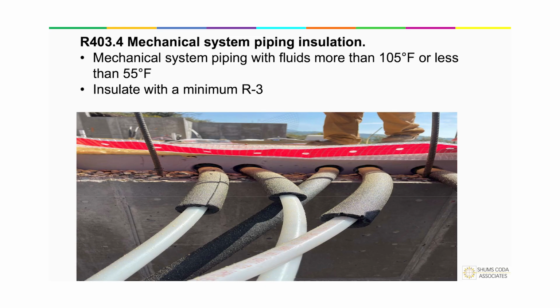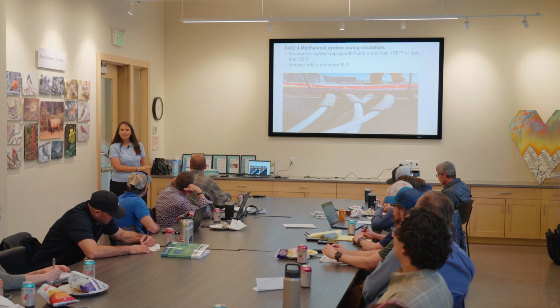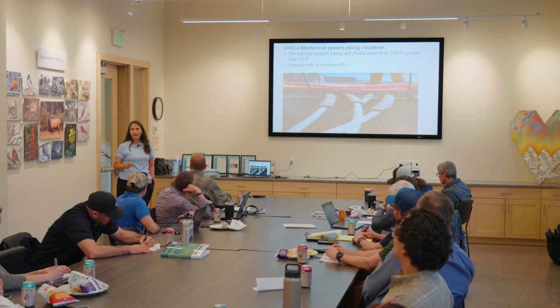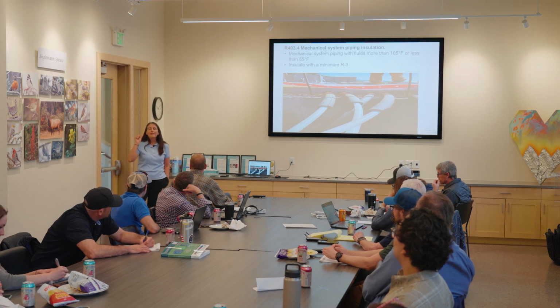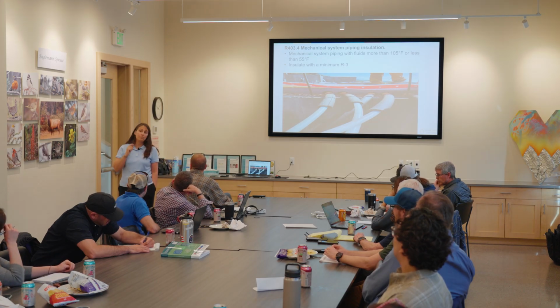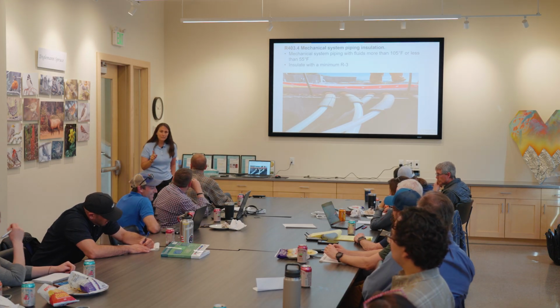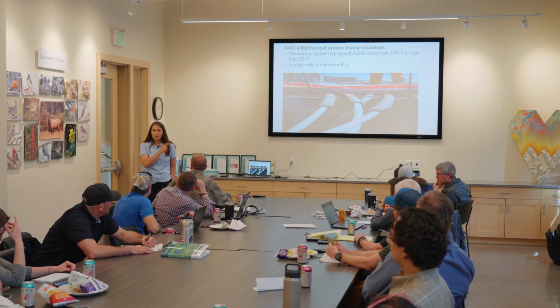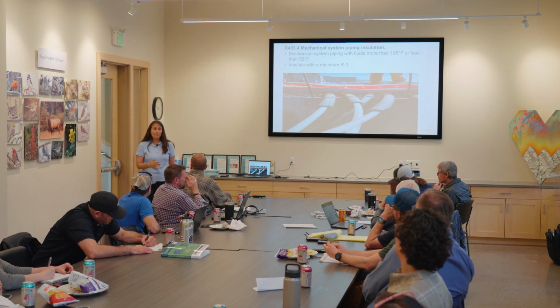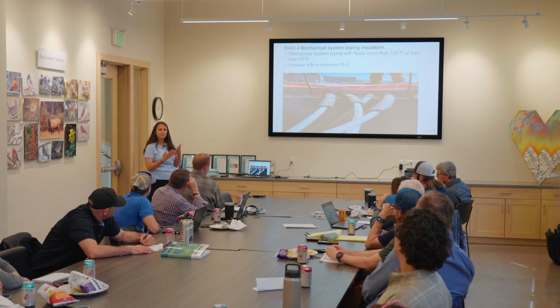Unfortunately, I went out to do an inspection. Never in a million years did I think this was an issue. I never want to have a conversation again where I say, I am so sorry, you cannot insulate the tubing in your floor heating and you have to remove it, because they did a really good job with it. That is not a conversation I ever want to have again. It's really hard because they say, but the energy code says I have to. He was not wrong. But how's it going to heat? Exactly. First year mechanical?